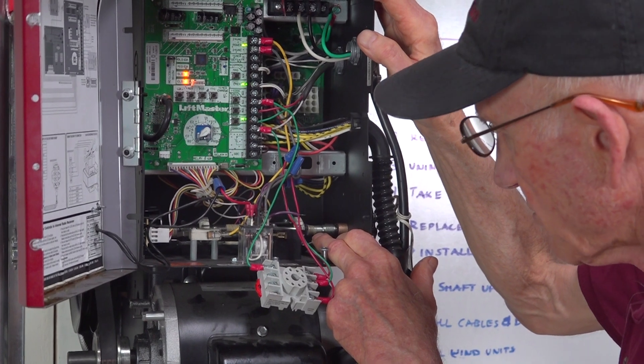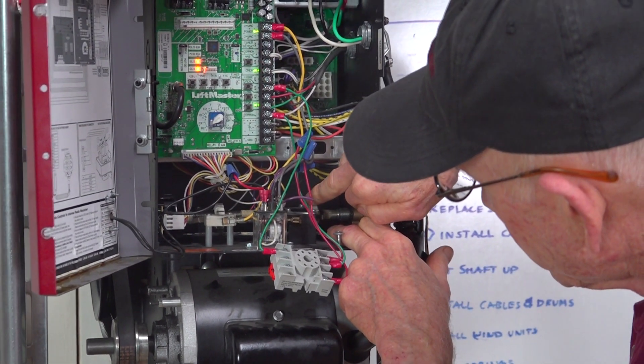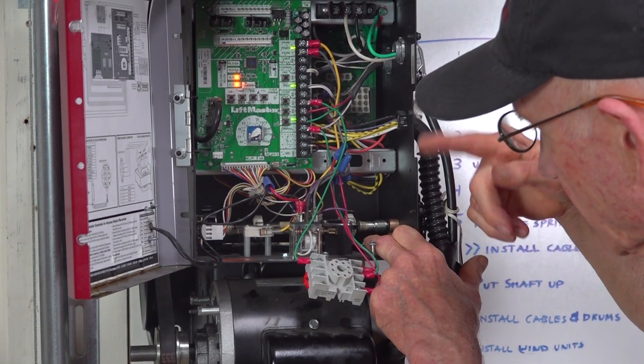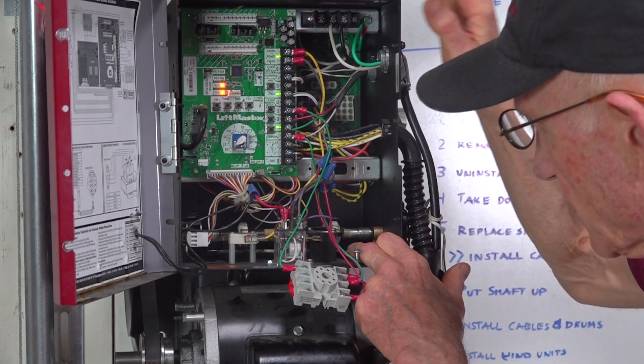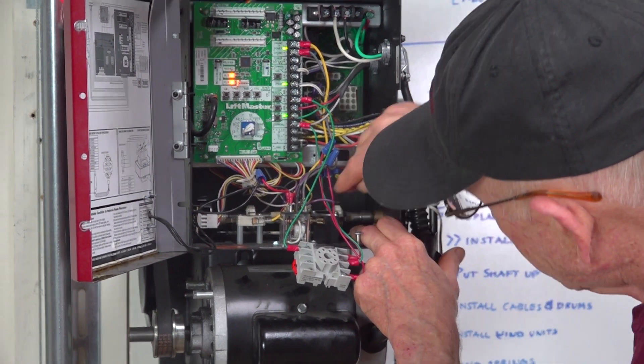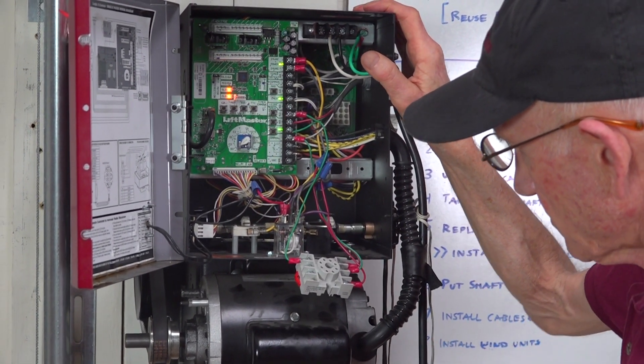So, to adjust the travel or the limit, you can move the nut away from the switch so that it will travel further, or move it toward the switch so that it will not travel as much.